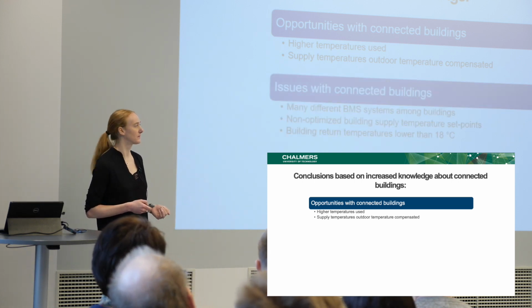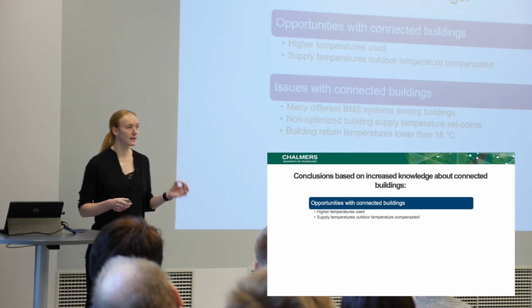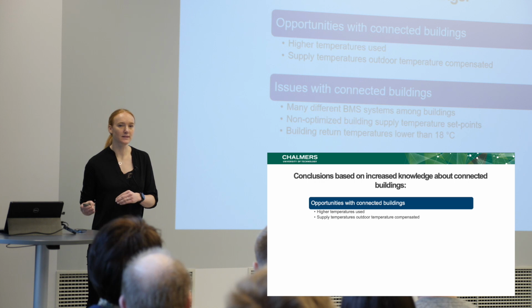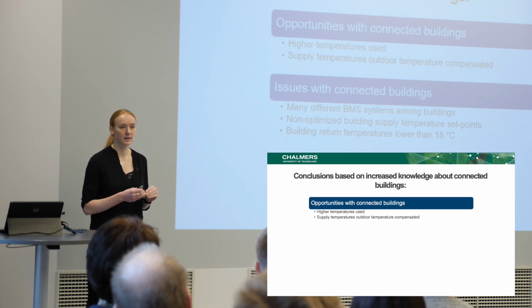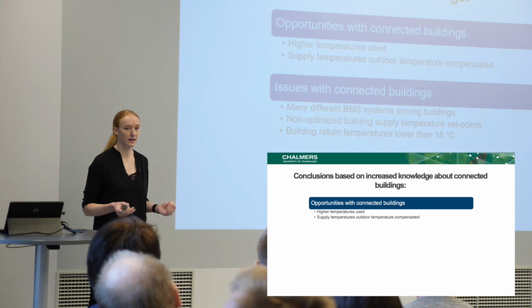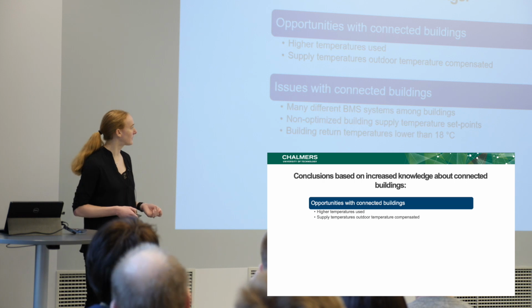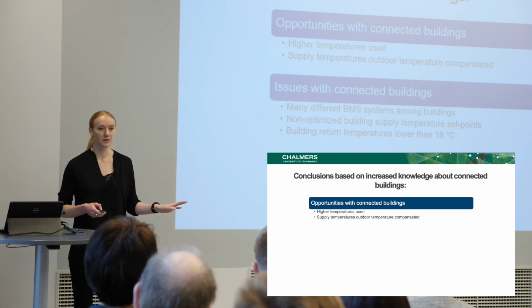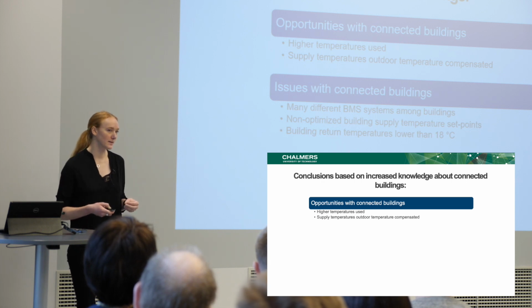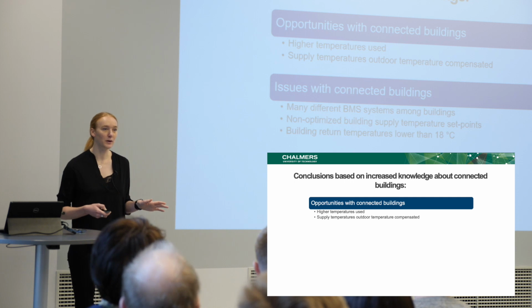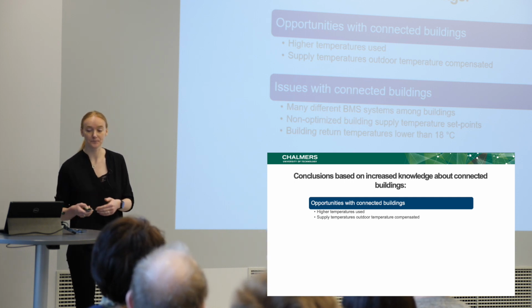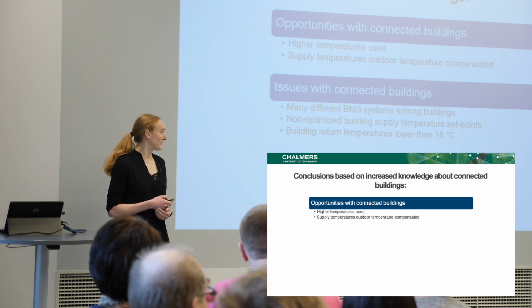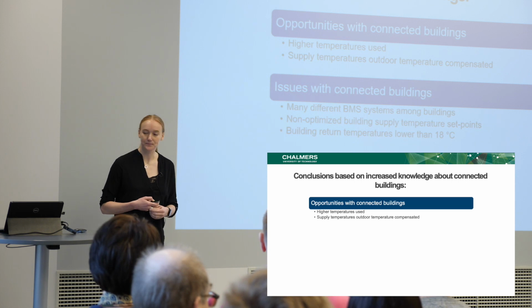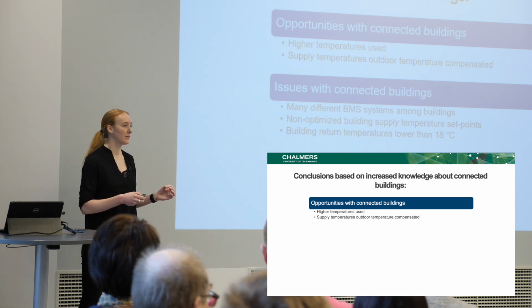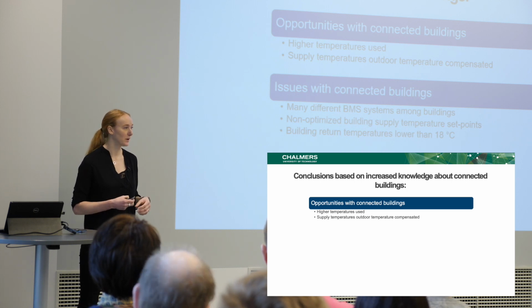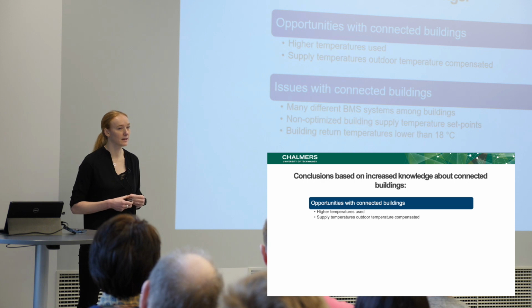However, there are also some issues that we have seen in the connected buildings, and it's mainly linked to the fact that everyone does it their own way, basically. There are a lot of different building management systems and ways they are controlled. Some are much more sophisticated than others. Some building owners just set their supply temperatures to whatever the design engineer has suggested, and they never follow up on them. So let's say they set them to 8 degrees, regardless of what the actual cooling demand of the building turns out to be. So, non-optimized building supply temperature set points in many buildings. And that also leads to the return temperatures being anything between 9 up to 18. So there are many buildings that do not reach the 18 degrees.